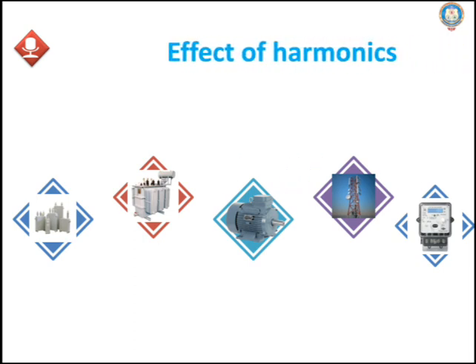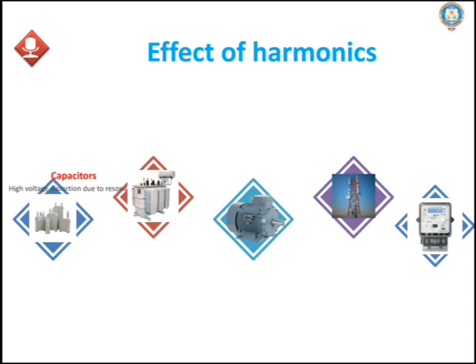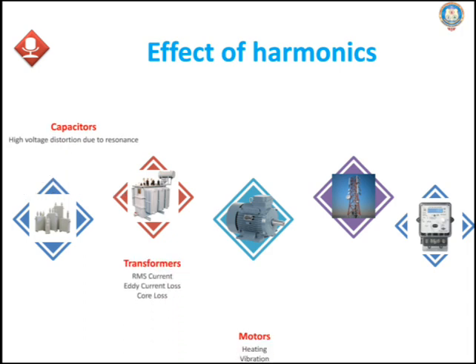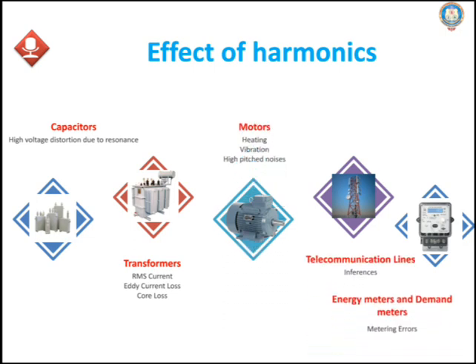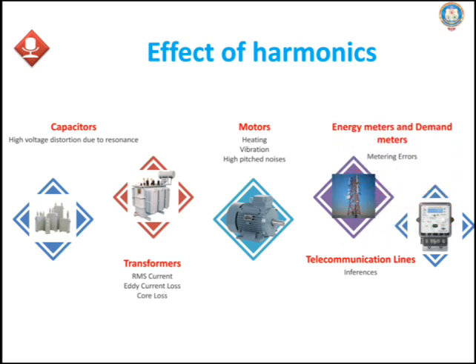What are the effects of harmonics? The effects of harmonics are seen in capacitors, transformers, induction motors, telecommunication lines, energy meters, and demand meters. In capacitors, it causes high voltage distortion due to resonance. In transformers, it increases RMS current, eddy current losses, and core losses. In motors, it causes heating, vibration, and high-pitched noises. In telecommunication lines, it causes interference. In energy meters and demand meters, it causes metering errors.